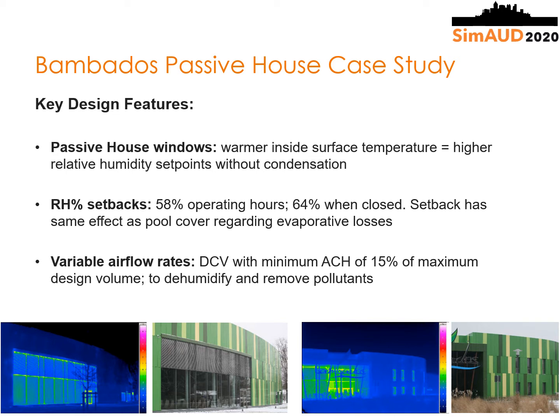So at the Bambados pool, they have passive house windows, which, like I said before, provide a warmer inside surface temperature, which equals higher relative humidity set points without condensation. Another thing that they did was have relative humidity set point setbacks. So they set it at 58% during the operating hours and 64% when they were closed. So in their studies, they found that the setback had the same effect as a pool cover regarding evaporative losses. Finally, they had variable airflow rates. They had demand control ventilation with a minimum air change rate of 15% of its maximum design volume.